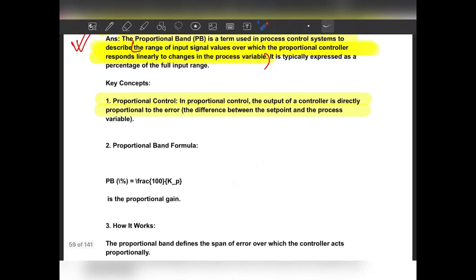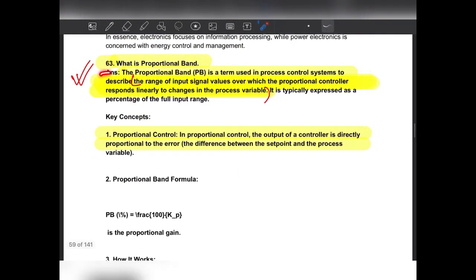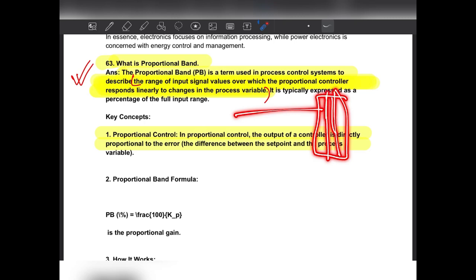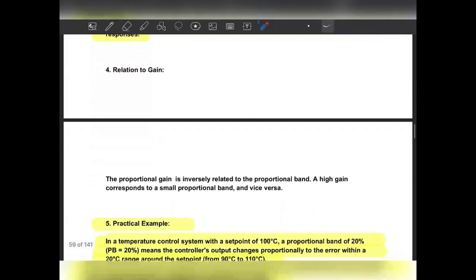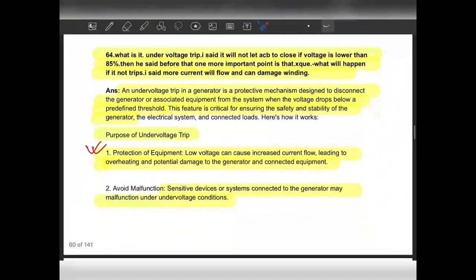Proportional controller I already explained before also, and sometimes they ask what is the proportional band. So read this one. Proportional band is a term used in process control systems to describe the range of input signal values over which the proportional control responds. It means the proportional control will respond only to a certain range of input. A band has some range, and within this band the proportional controller will act, and that range is termed the proportional band. Okay, so this is the proportional band. I already explained, no need to explain again. Move on to the next.